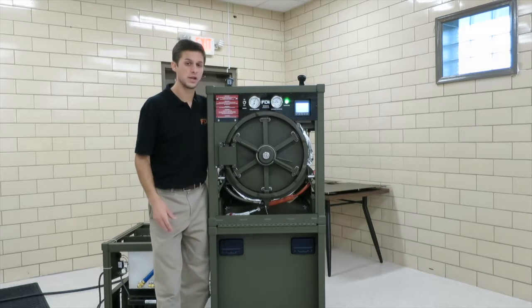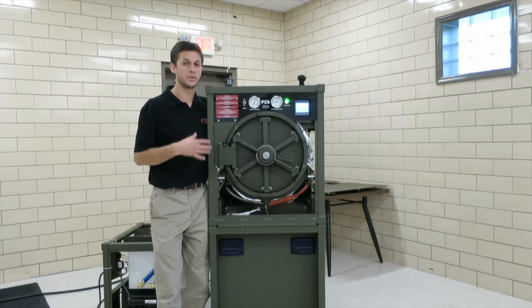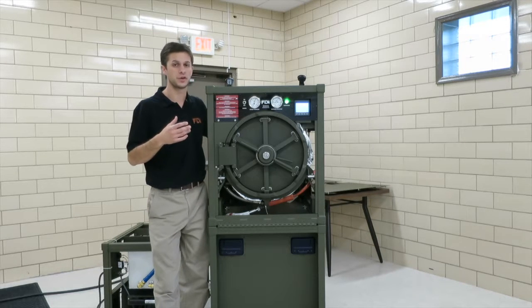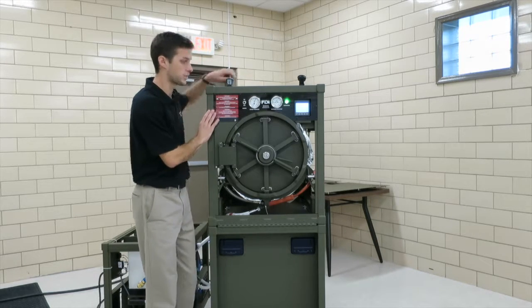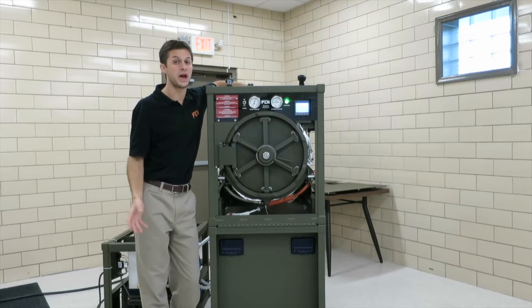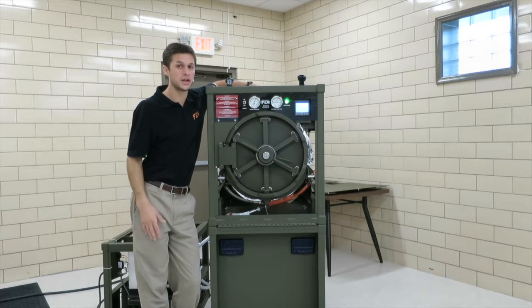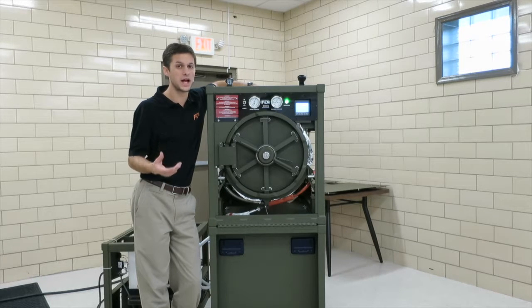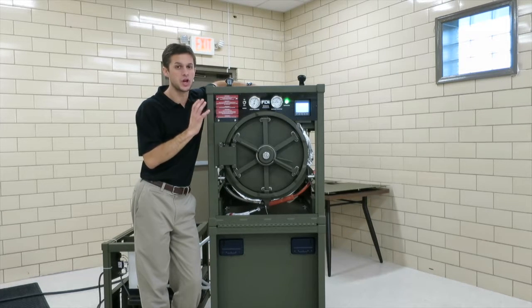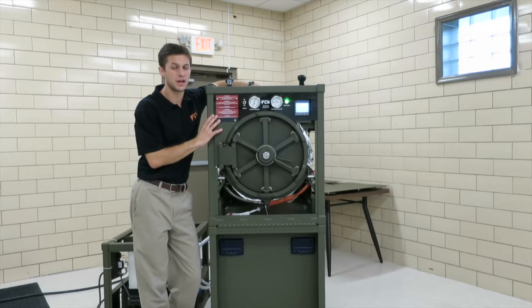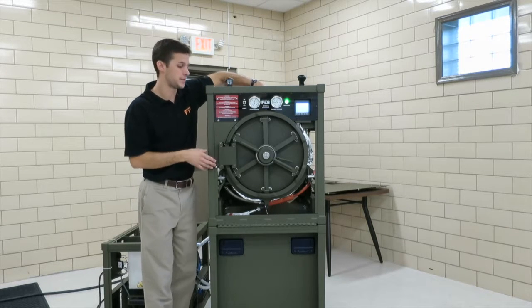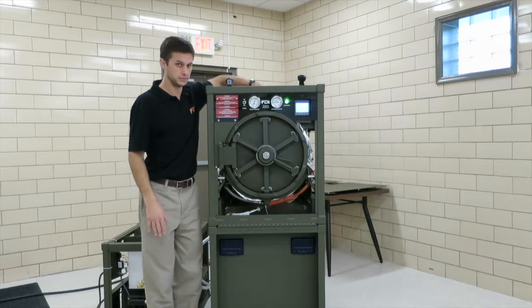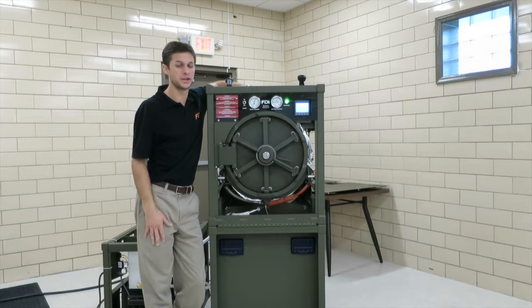That's a very important alarm to get when you first set up this unit. The first time you set up the P2131 sterilizer, if you haven't added water, you should get that 02 low water level alarm, which is a good sign because you know that switch is operating correctly. It's a good check for the operators, but if they ever have questions for you, the maintenance personnel, that's what the 02 low water level alarm is.